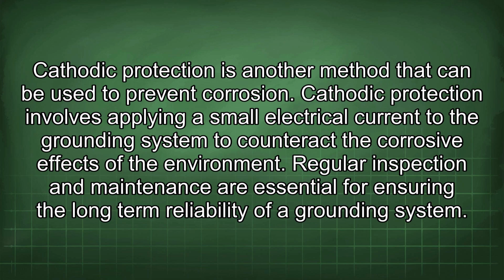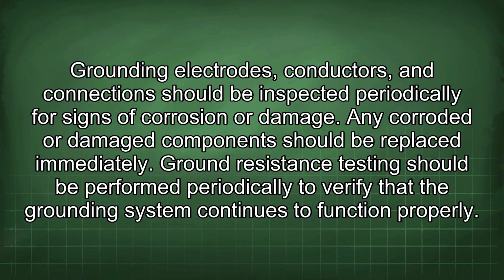Regular inspection and maintenance are essential for ensuring the long-term reliability of a grounding system. Grounding electrodes, conductors, and connections should be inspected periodically for signs of corrosion or damage. Any corroded or damaged components should be replaced immediately. Ground resistance testing should be performed periodically to verify that the grounding system continues to function properly.